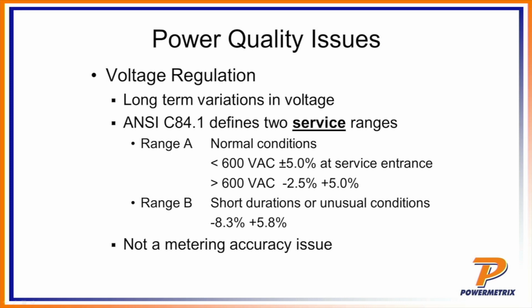And so what you see is that you have a little bit more leeway, goes from plus 5% to plus 5.8%. On the low side goes from minus 5% down to minus 8.3%. And so they expect a little bit more of a sag if you have a short-term issue. Once again, this is not a metering accuracy issue. The meter is designed to average it over the course of a long period of time, and so voltage regulation is really not going to affect the meter because it's designed to work over a wide range of voltages, and it's just going to average that out.